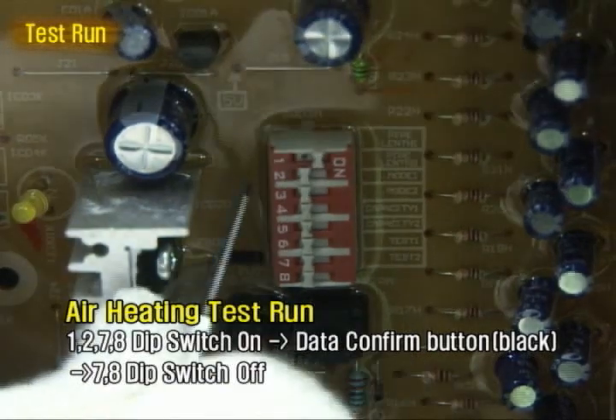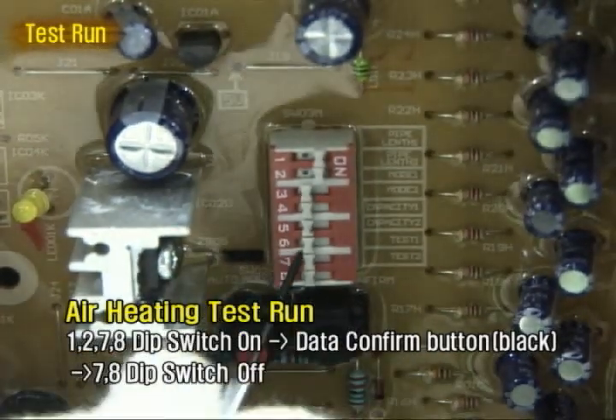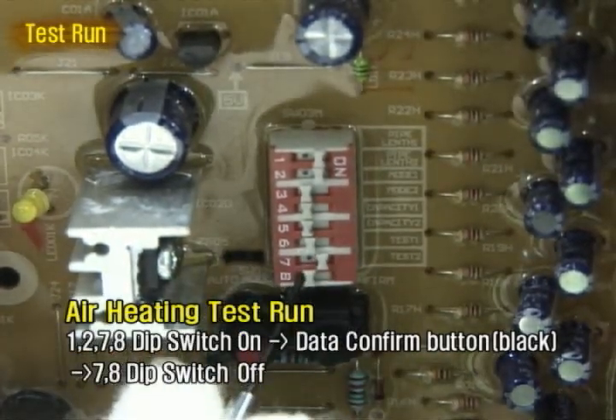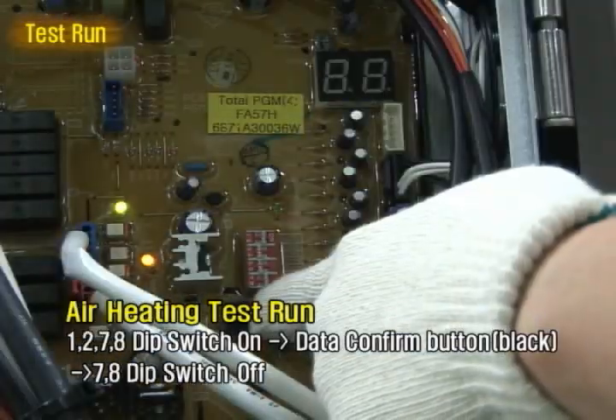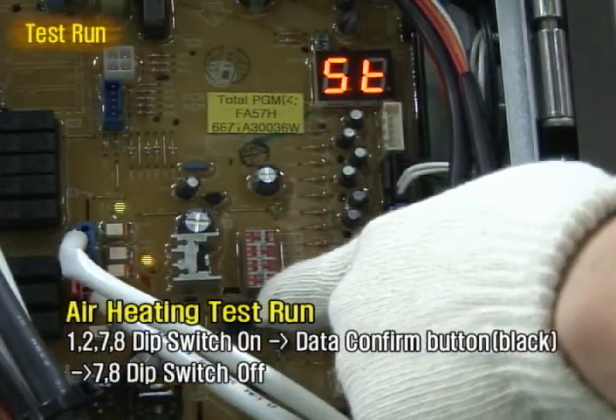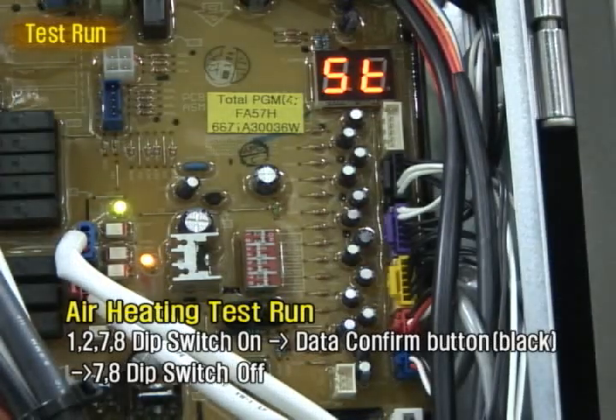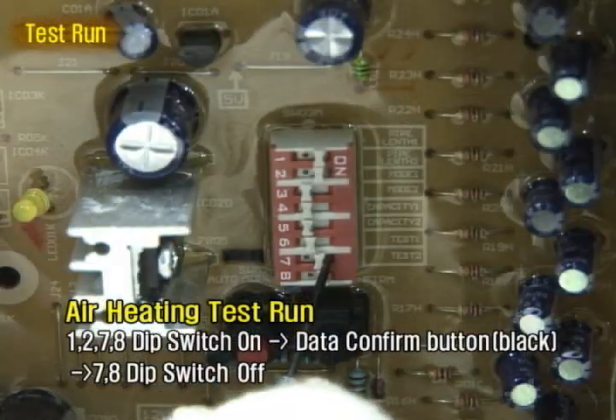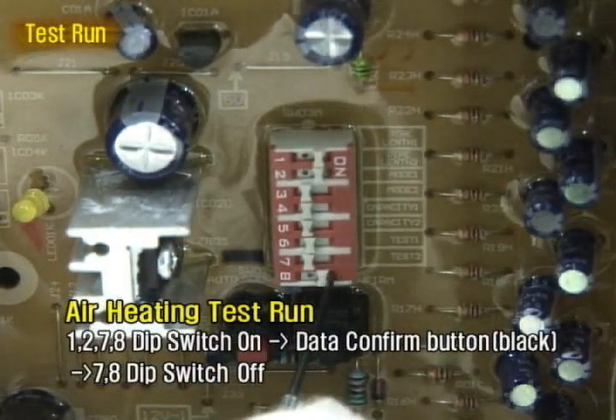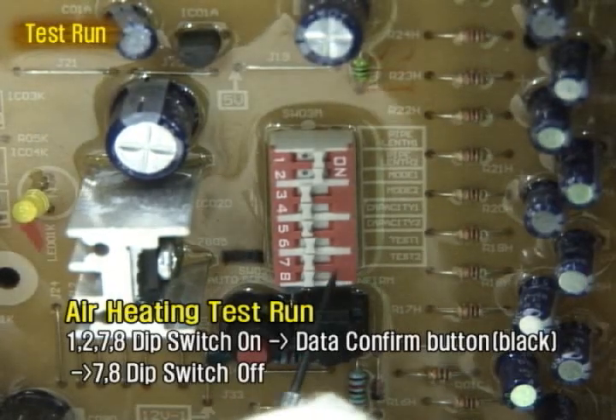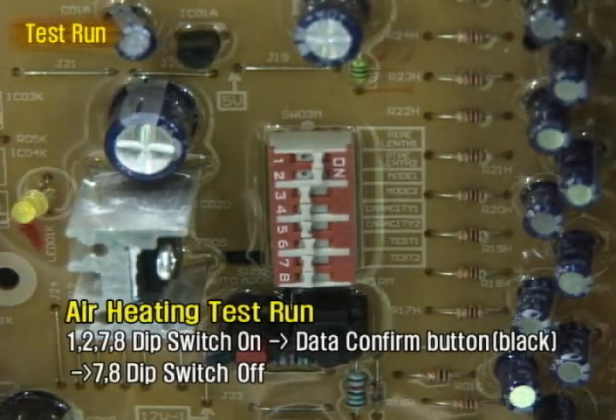For heating mode, set the dip switch of 1, 2, 7, and 8 to on and press data confirm switch. Then ST letter appears on the segment LED. Set the dip switch of 7 and 8 to off to start heating test run.